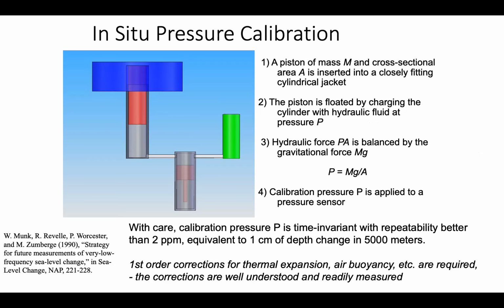We use a device known as a deadweight tester, also known as a piston gauge. Conceptually it's very simple: imagine a piston of area A supporting a total mass M, fitting into a closely fitting cylinder. You fill the cylinder with some working fluid, could be a gas, and pressurize the fluid until you float this piston assembly. Then it's simply a force balance—the hydraulic force, pressure times area, is matched by the gravitational force M times G. So you can show that P equals mg over A, and M, G, and A are all things you can measure.